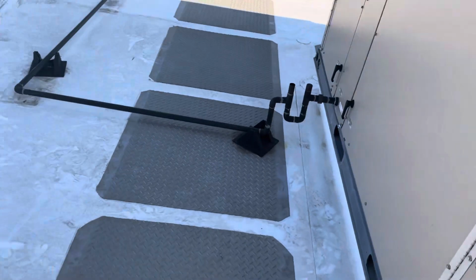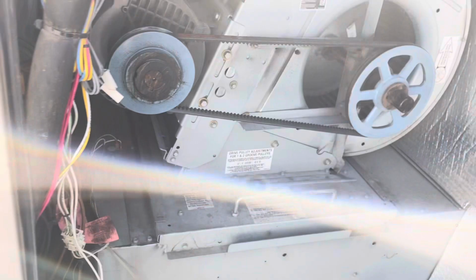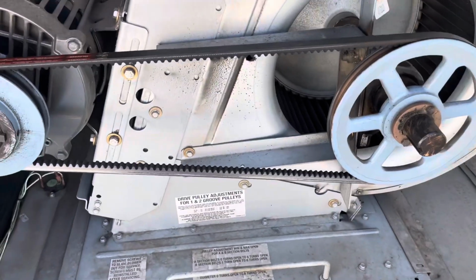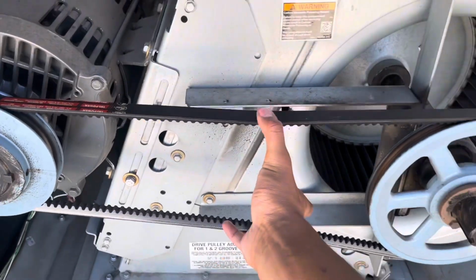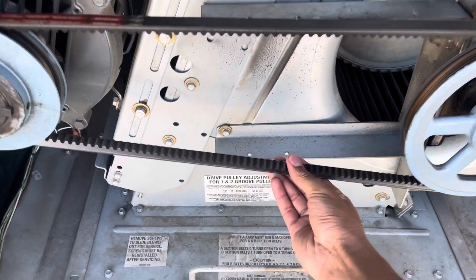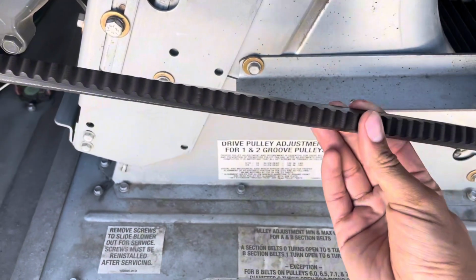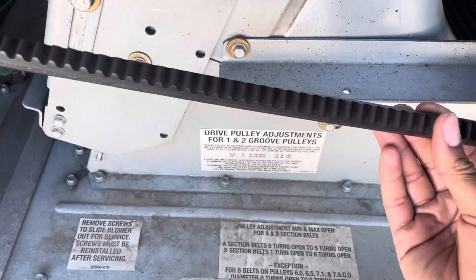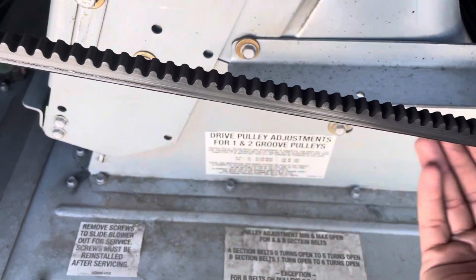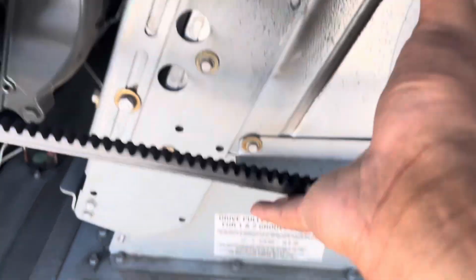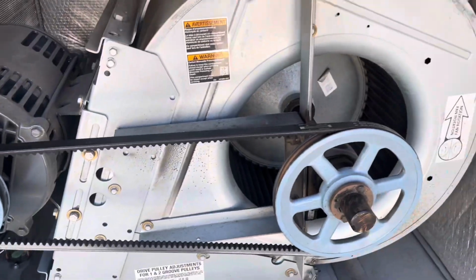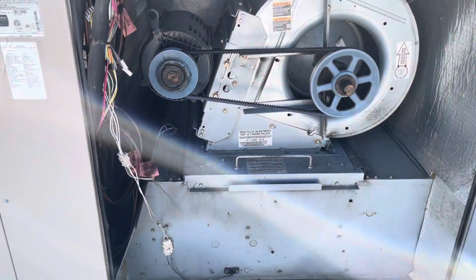Obviously too, when you're doing a heating PM, check the belt, because you still need the blower to run to move the air. So this belt is nice and tight. I don't see any cracks. The belt is in pretty good shape. All right, so let's turn the unit on.